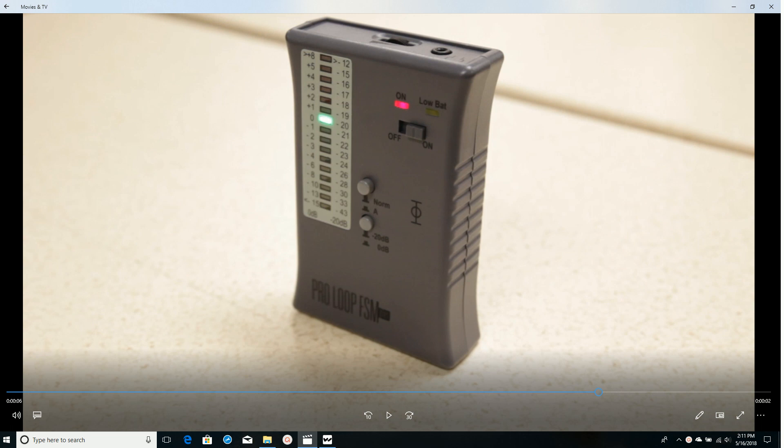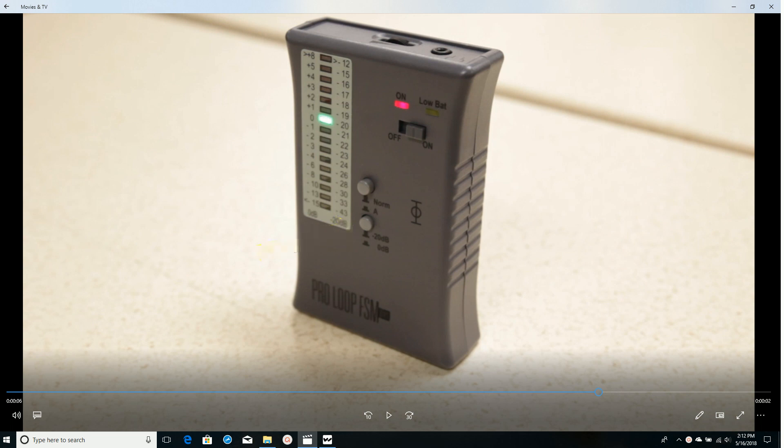You will need a Williams Sound field strength meter for measuring the field strength. Set the top button to the normal or out position and the lower button in at the 0 dB position. A 0 dB point on the scale references a field strength measurement of 400 mA/m.